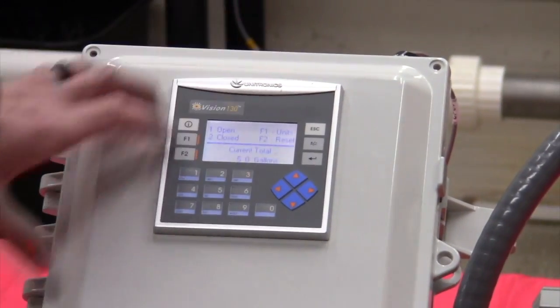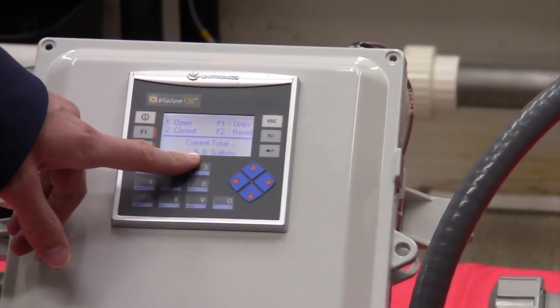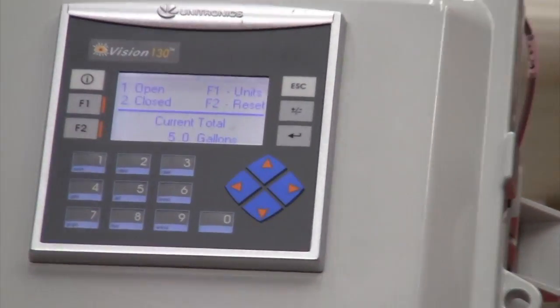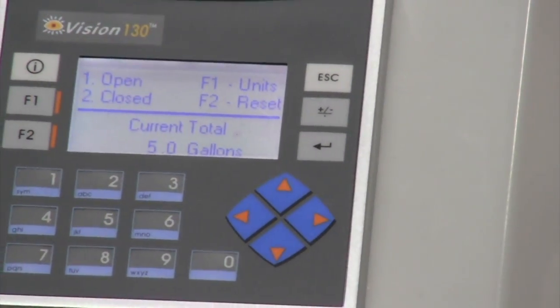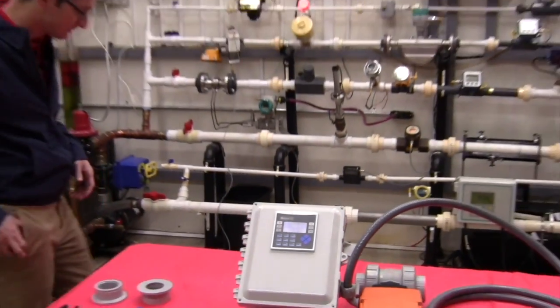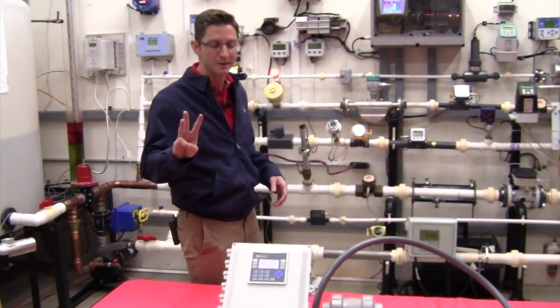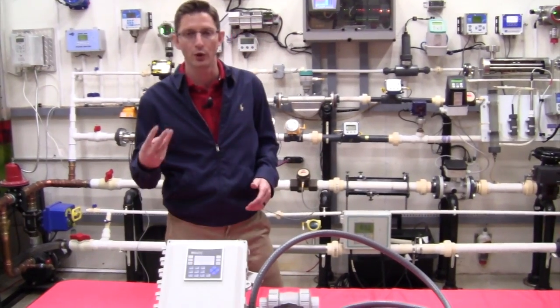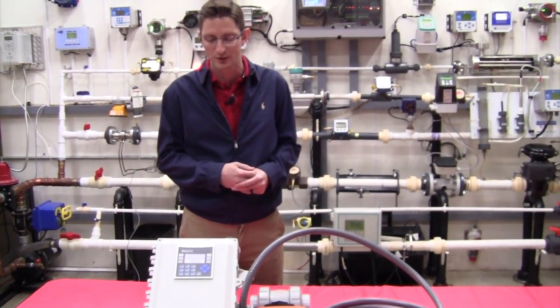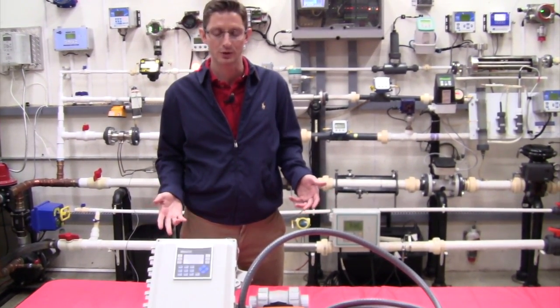So if I back out, go into manual, it shows me that I've flowed exactly 5 gallons, which is the size of my bucket. So I would personally suggest that anytime you do this, you do it 3 times. So in the case of a pool store, you're going to fill 3 different 2.5-gallon jugs. Take the average across those 3.